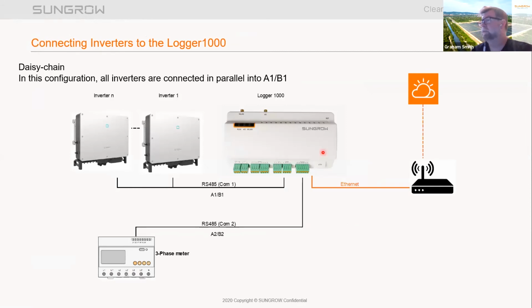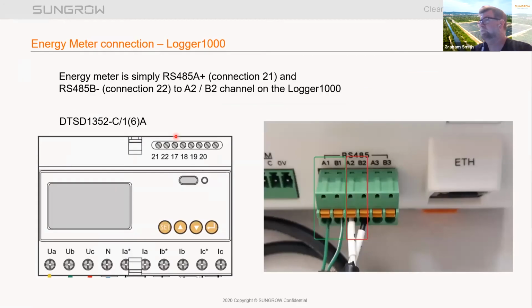Daisy chain, once again, a bit of an elaboration on it here. You basically daisy chain each inverter into the RS485 and the energy meter to the RS485 there. In this configuration, you could have up to 29 inverters connected to it. And there's a bit of a zoom of this. This is the Logger 1000, the RS485 connections. And this is the one we have at the training center.